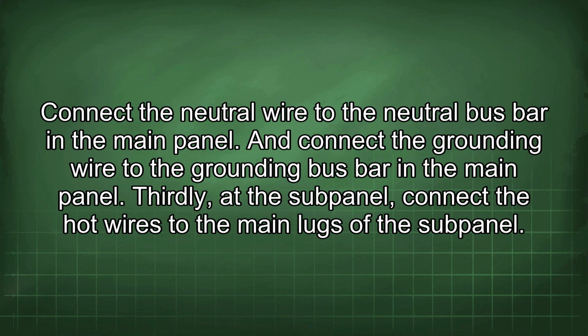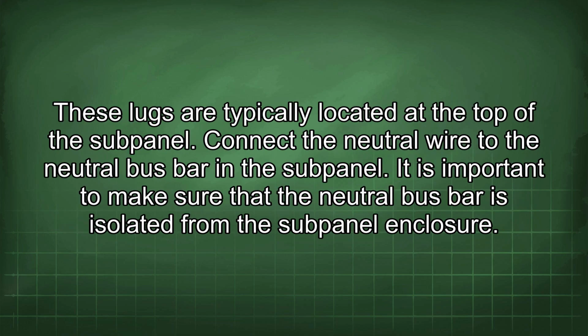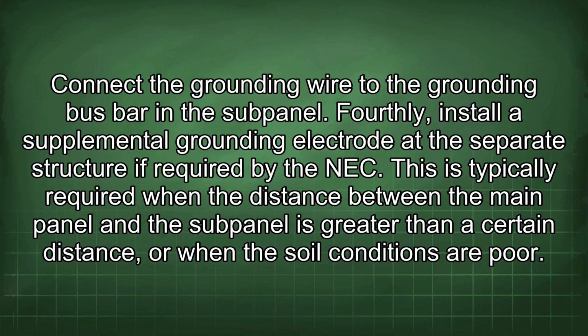Thirdly, at the subpanel, connect the hot wires to the main lugs of the subpanel. These lugs are typically located at the top of the subpanel. Connect the neutral wire to the neutral bus bar in the subpanel. It is important to make sure that the neutral bus bar is isolated from the subpanel enclosure. Connect the grounding wire to the grounding bus bar in the subpanel.